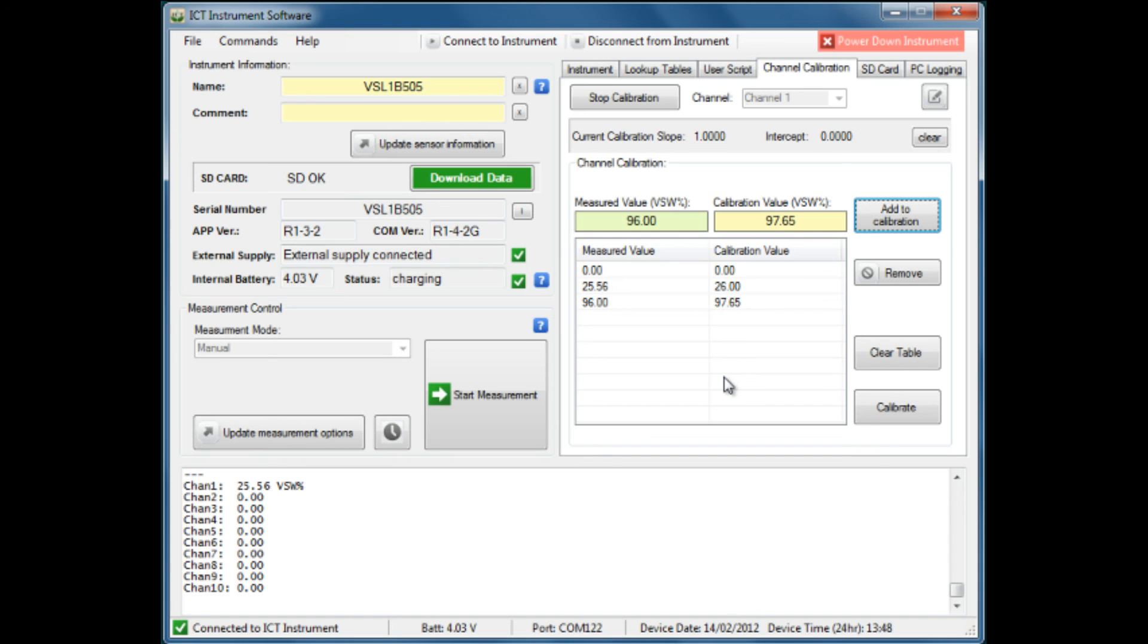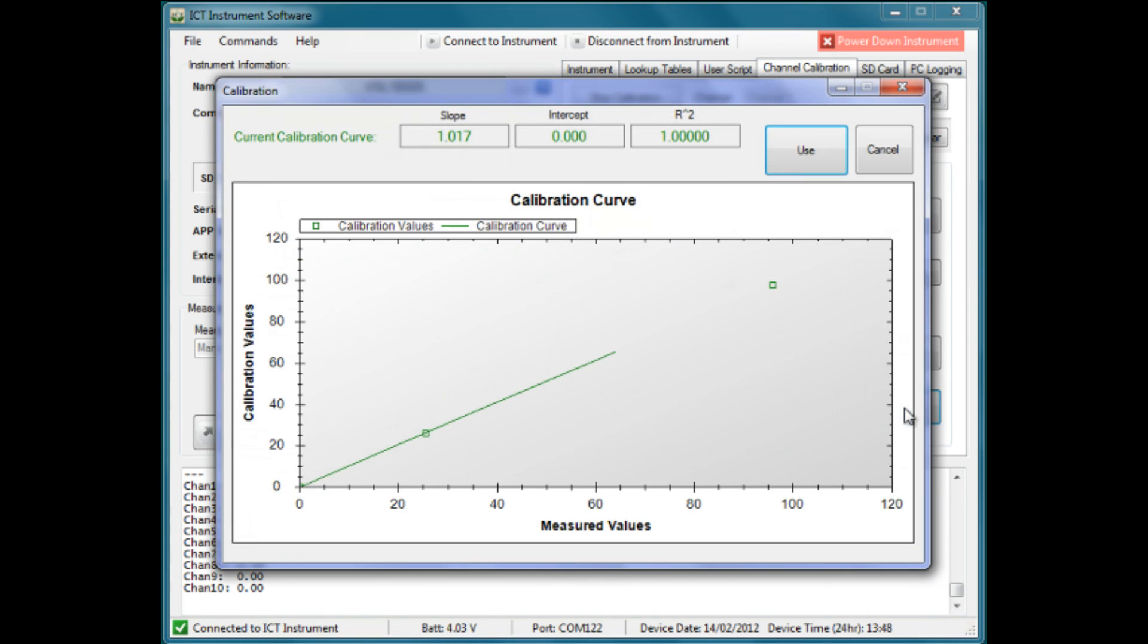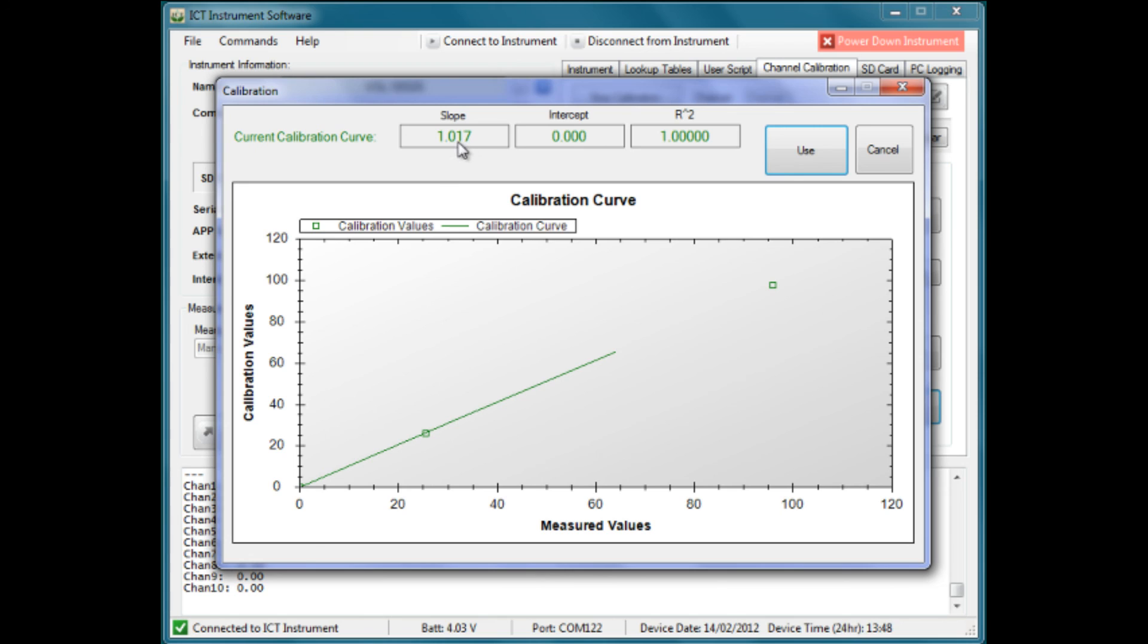The software will use this to apply a factor to the measurements obtained from this sensor. Having done that, we then hit the calibrate button and notice that the software has produced a calibration curve starting at zero and has a slope or correction factor of 1.017.